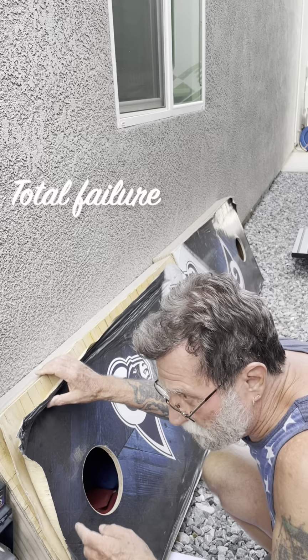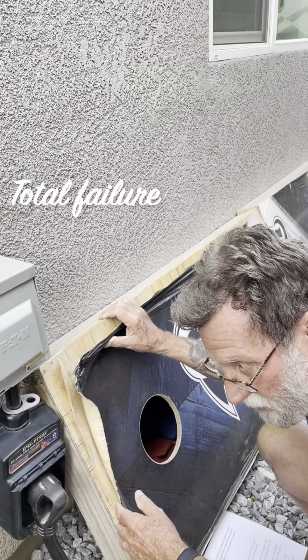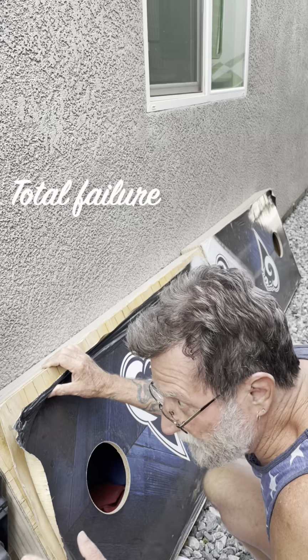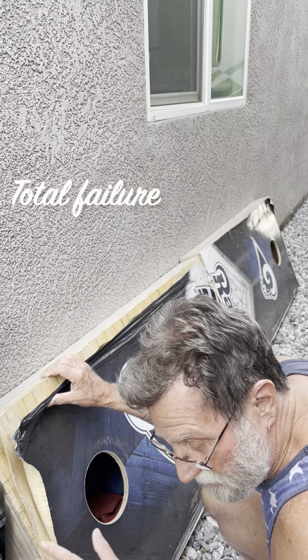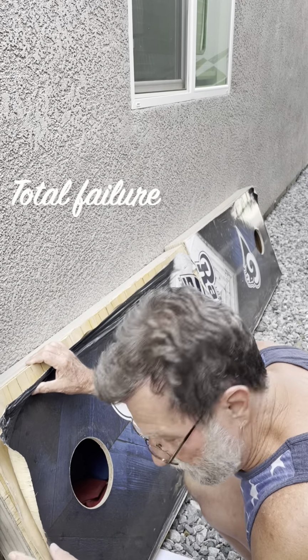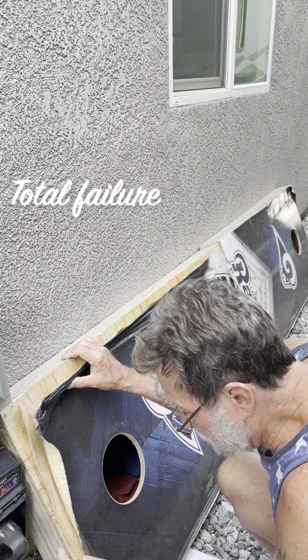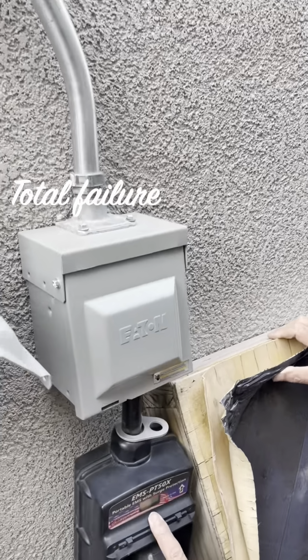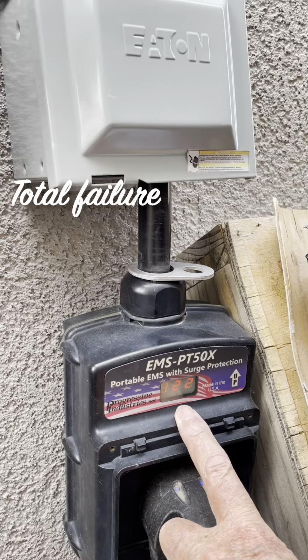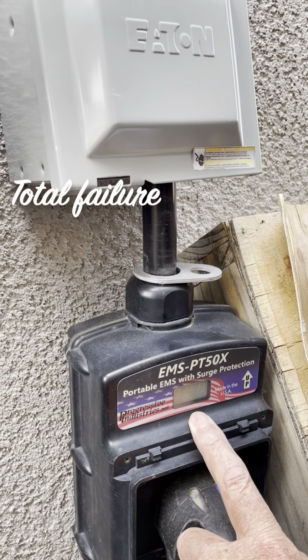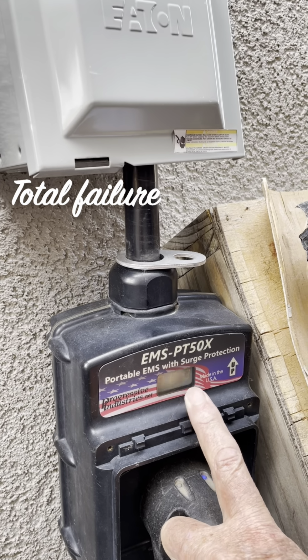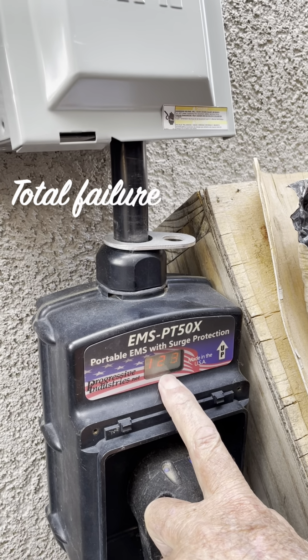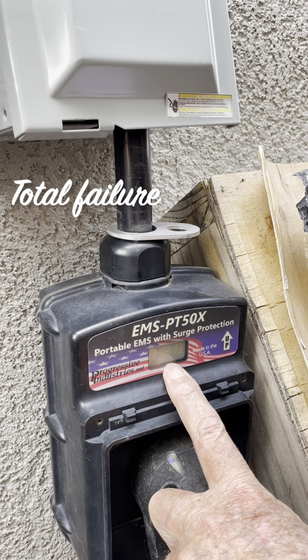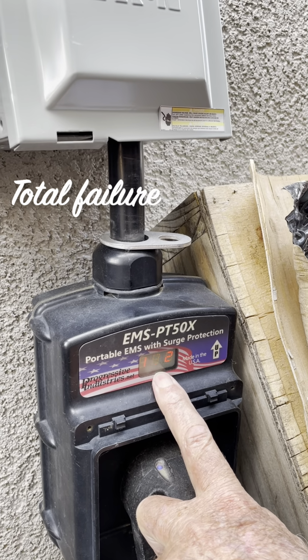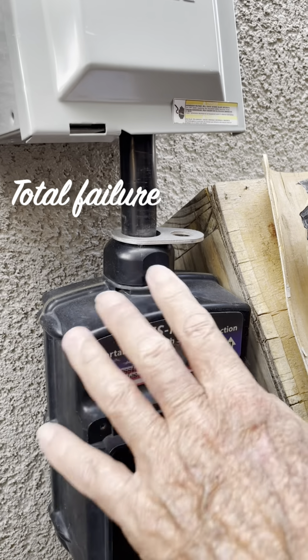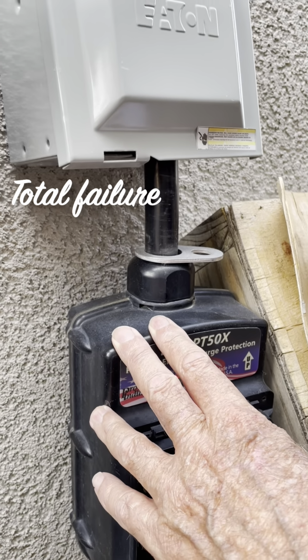All right, so you would go to your pedestal and look for a tripped circuit breaker. Right now we're someplace where we're using power from a house, but I will show you the breakers in the next segment. Does your EMS show that you have power? If you don't have an EMS, of course, it won't show power. This shows no errors. Line 1, 123 volts. Line 2, 122 volts. So according to my EMS, I have power on both legs.